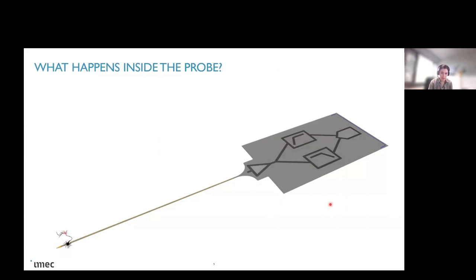So what happened in this probe is we will capture a neural signal with one electrode. This is going to travel through the shank and arrive to a first amplification stage. After this in Neuropixels 1, we are splitting the band into AP and LFP signal components, low frequency and high frequency components. And after that is going to analog to digital converter that is going to digitize the signals. And all this is done in parallel then for 384 channels.